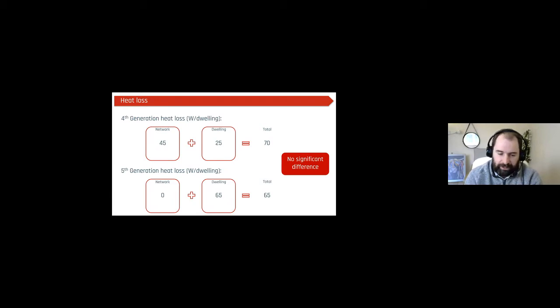If we look at fifth generation heat loss, again, this is within the communal systems. You've got network, so there will be some heat loss, but it will be marginal. Just for the sake of argument, I'd say there's zero heat loss from your network. Because you're storing water in your hot water cylinder within a flat, you typically have about 65 watts for about a 170 litre modern hot water cylinder. So when you look at the network and the dwelling heat losses in total, there's not a significant difference between the two approaches, and that's down to the fact that you don't have to store hot water in a fourth generation system.